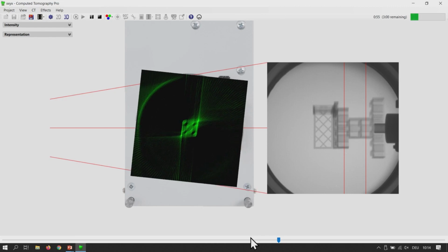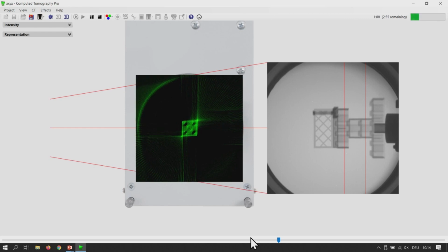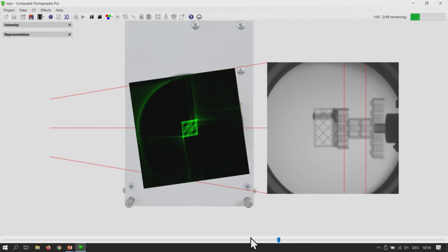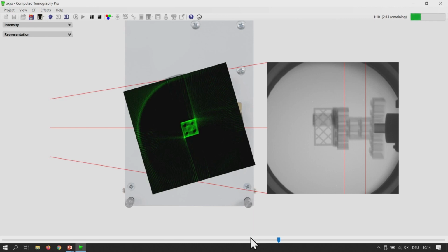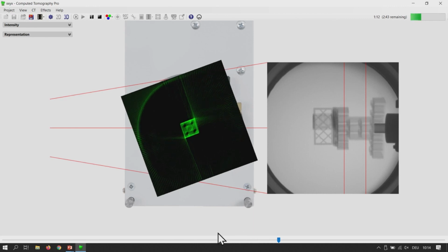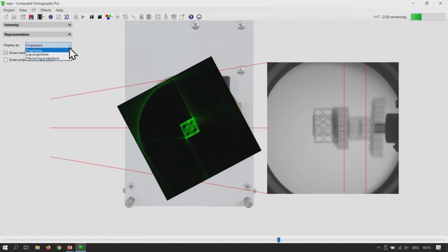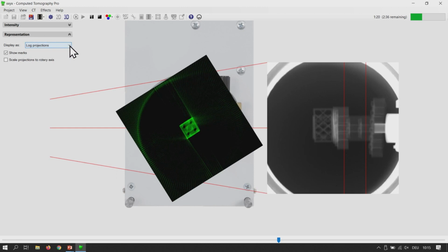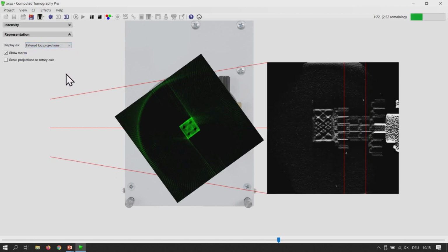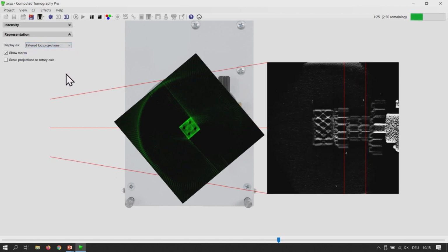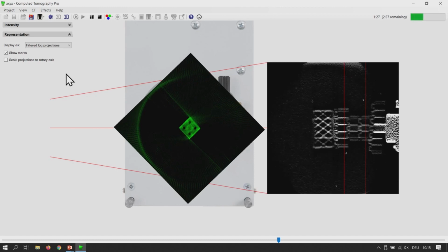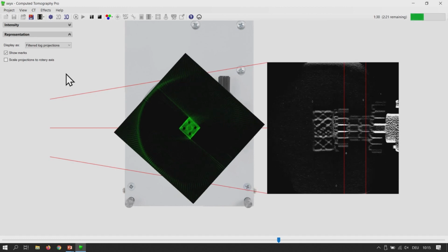And so what we are seeing here is how the image is reconstructed in real time. There are a lot of rays being shot through the sample, and they are added up and calculated on the right-hand side. To be mathematically precise, it is not the projections that we are adding up, but a logarithm of the projections. And this is then high-pass filtered with a special Fourier transformed filter, which makes it mathematically correct.